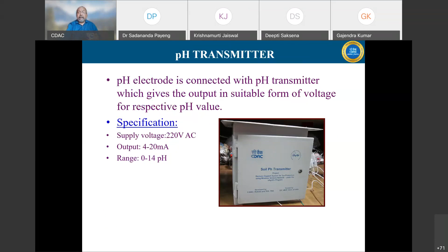We also had a pH electrode calibration methodology. Any sensor, for your information, has to be calibrated at regular periodicity. Unless calibrated, sensor values have no meaning—like a thermometer at home: if it reads 98 degrees Fahrenheit you trust it, but if it varies, your decisions go haywire. So sensor calibration, especially for agricultural or industrial use, needs to be done regularly.